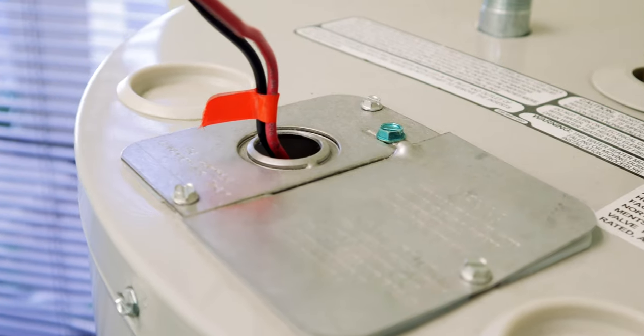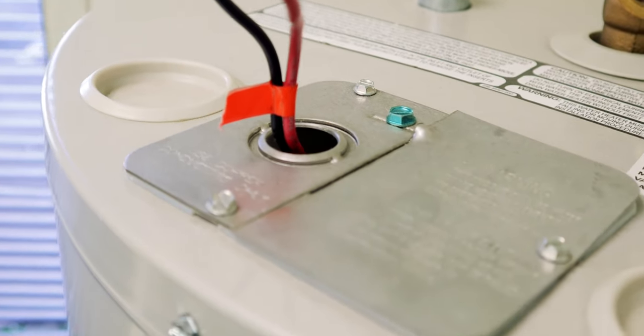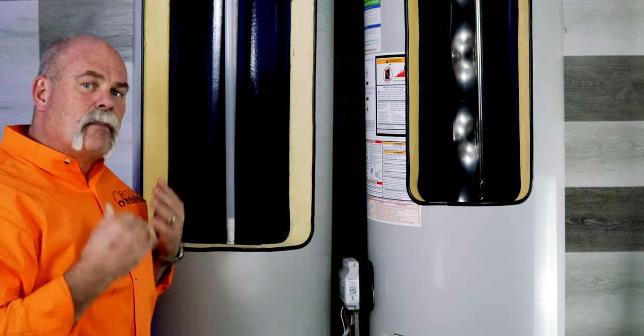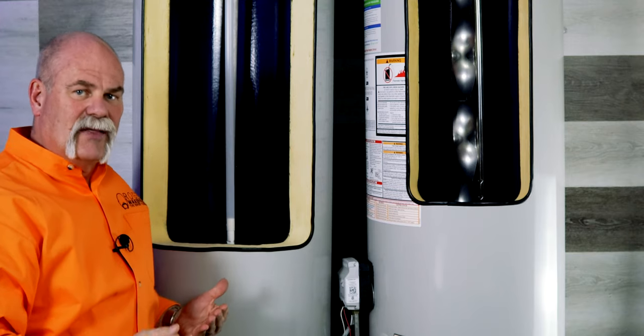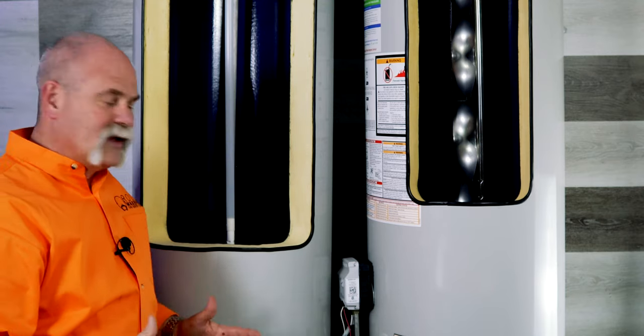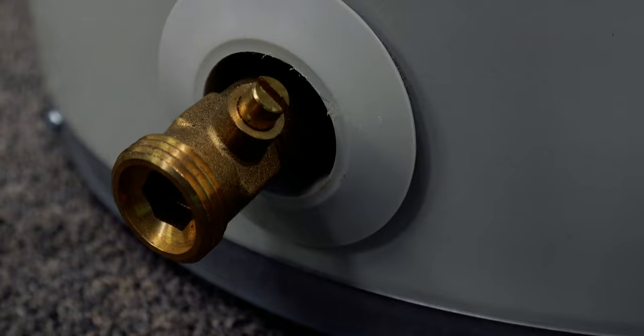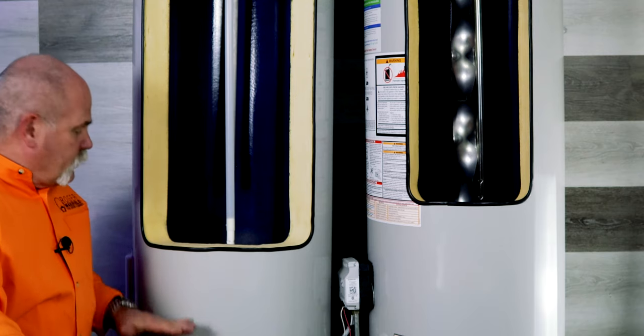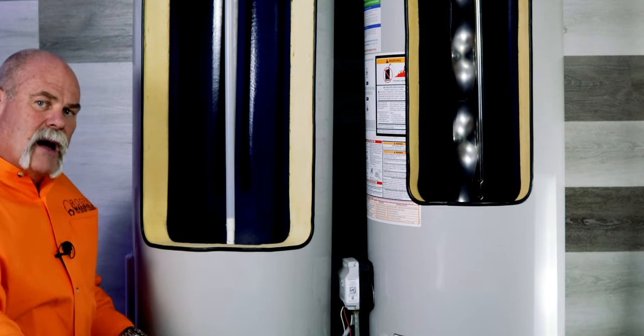On an electric water heater, at the very top you've got the panel where your power comes in. Test it, make sure the breaker's turned off before you open and undo anything. The drain valve is really important - if you flush this water heater every year, you'll keep the calcium and magnesium out of the bottom and make it last longer.